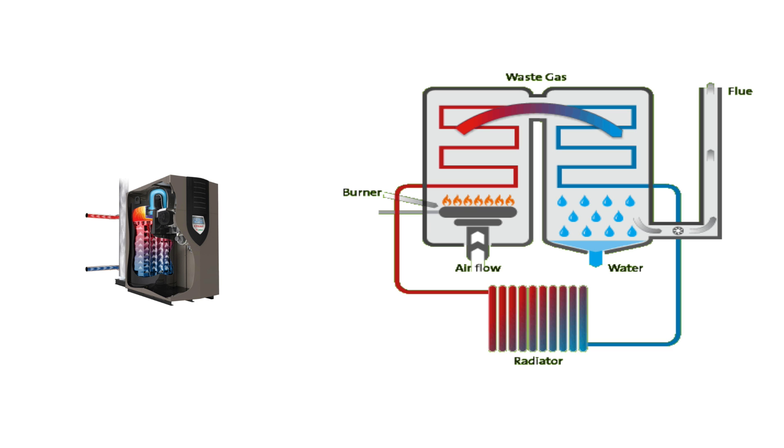Finally, we've talked about condensing gas boilers. Here's an example of a condensing gas boiler. And in that case, our gas heat heats water, and then the return water is cool enough that it actually condenses the hot water vapor produced by the combustion process to liquid water. And that's how we get the full maximum gross heating potential out of our fuel. So you'll notice that the hot water goes, it circulates this way. So the cooling gases come in contact with the cool water. And as Jeff Pellerin would say, it wrings the water out of those stack gases, condenses the water, and allows us to extract maximum amounts of heat.